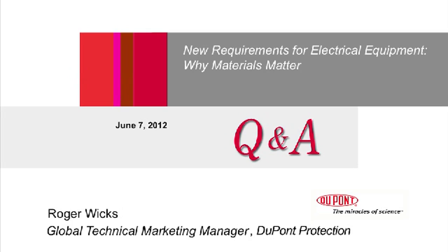Roger, another one has come through. How is the chemical compatibility of type 418 NMN? Yeah, so let's say this question is related to the ATF example I gave earlier. The chemical compatibility of the 418 NMN would unfortunately be no different than a normal NMN, because all you've done by replacing the 410 with the 418 paper is improve the resistance to partial discharge. Chemically, the 418 is similar to the 410, and unfortunately the film is no different in that situation. Where manufacturers have had to look at chemical compatibility in motors that have ATF, a film with higher chemical compatibility has been necessary to withstand the effects of things like the ATF.